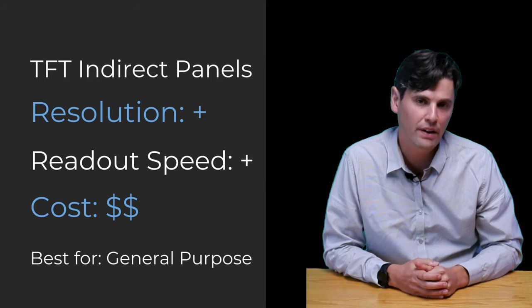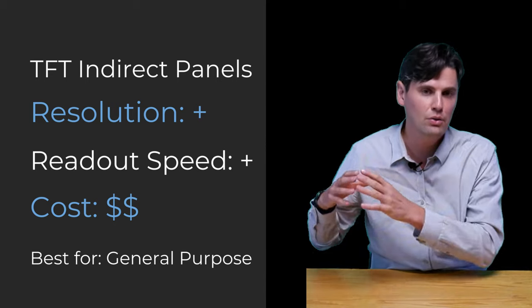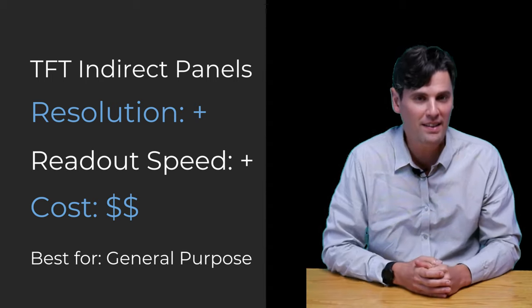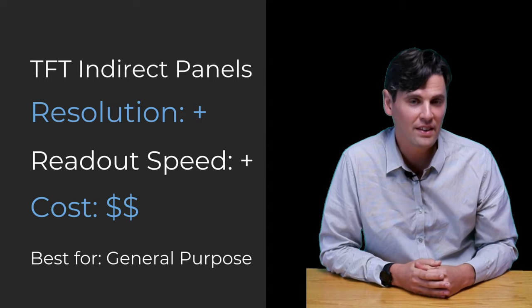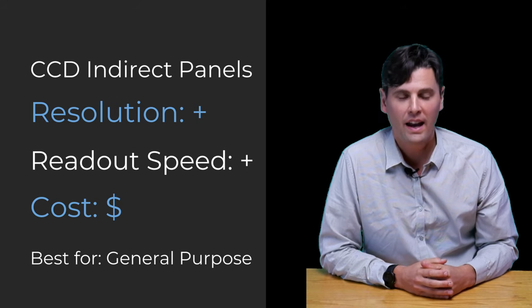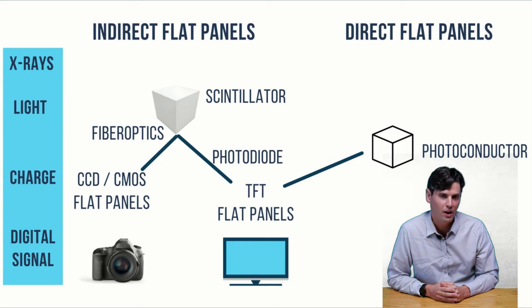For general radiography, the choice is between CCD and TFT arrays. TFT arrays are more common in the field and are more dose-efficient because no photons are lost in the light demagnification process required by CCD-based systems. CCD-based systems are generally a little less expensive than TFT systems. So at a high level, the trade-off is dose efficiency versus expense, with TFT being the more common choice for general radiography.